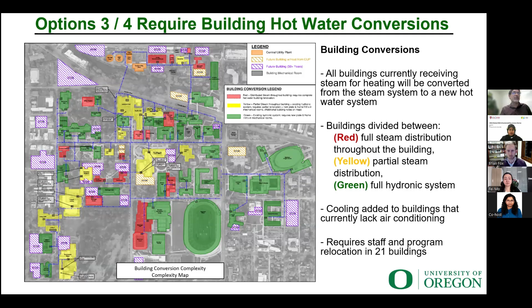Option 4 builds on option 3. This is a field adjacent to our plant where students play ultimate frisbee, soccer, and that kind of thing. We have significant simultaneous heating and cooling loads, but more heating in winter and more cooling in summer. This geo exchange field would let us capture all that summer cooling, which produces excess heat we don't have a use for in summer. We'd bury it deep, some 1,200 feet beneath this field, and retrieve it in winter. It builds on option 3, making it that much more efficient — the estimated annual emissions reduction is some 76%.